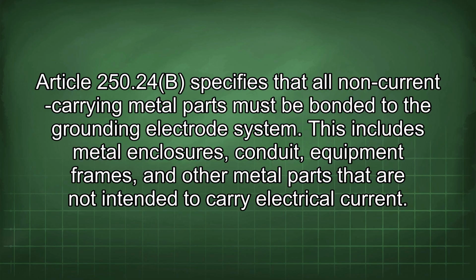Article 250.24(b) specifies that all non-current carrying metal parts must be bonded to the grounding electrode system. This includes metal enclosures, conduit, equipment frames, and other metal parts that are not intended to carry electrical current.